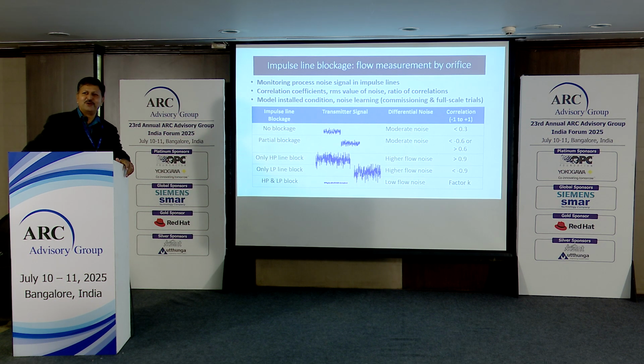You know that when we have flow, the process noise is seen by both sensor sides through the impulse lines. When one of the lines is choked, you have an amplified process noise being seen by the sensor, and also seen in the 4 to 20 milliampere output from the transmitter. And when both the impulse lines are choked, there is damped or low noise on both the limbs, and therefore the 4 to 20 milliampere signal is absolutely close to silent.